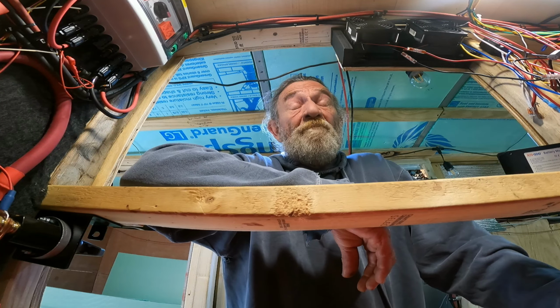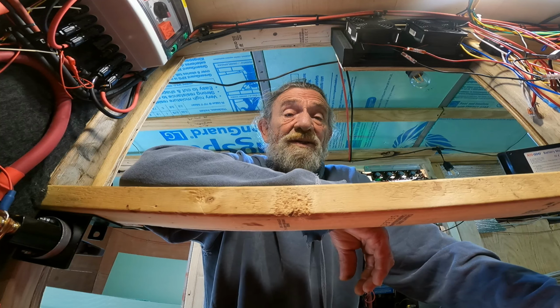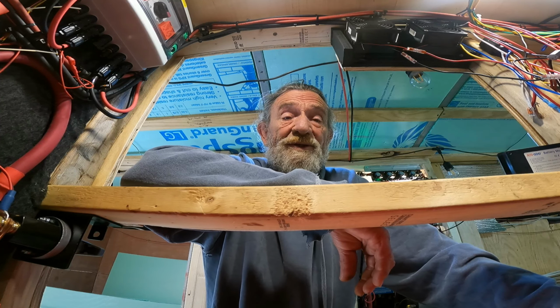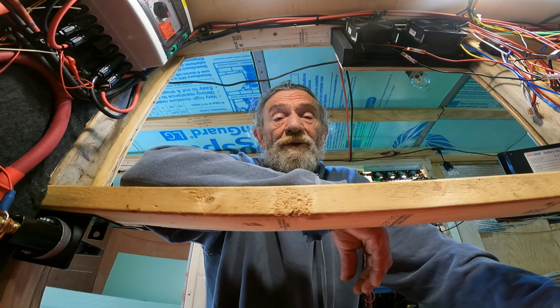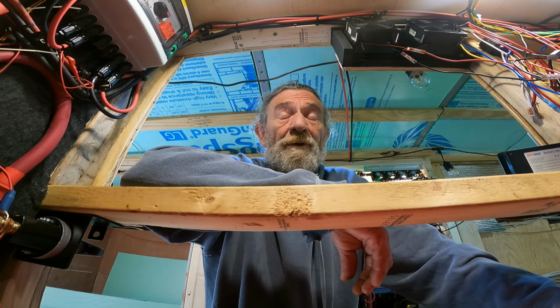So bottom line: inverters, VE bus, nothing else. No terminations required. Daisy chain them over, plug them into the VE.Bus inputs of the Cerbo, turn them on, they're there.